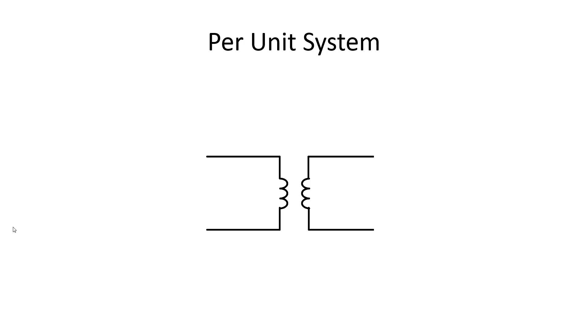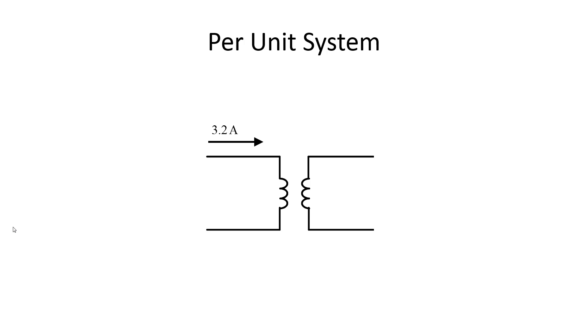What about currents? If we feed the rated current to the primary — 4 amps — we get the rated current of the secondary, 400 amps. That is, we feed 100% of the current in the primary and we get 100% in the secondary, or in per unit, we feed one per unit and get one per unit. Feeding 80% of the rated current, that is 0.8 in per unit, and then 50% — it holds.